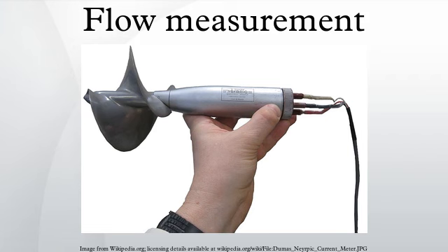Current meter. Flow through a large penstock such as used at a hydroelectric power plant can be measured by averaging the flow velocity over the entire area. Propeller-type current meters can be traversed over the area of the penstock and velocities averaged to calculate total flow. This may be on the order of hundreds of cubic meters per second.